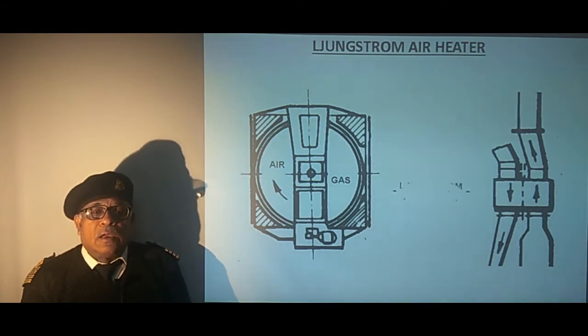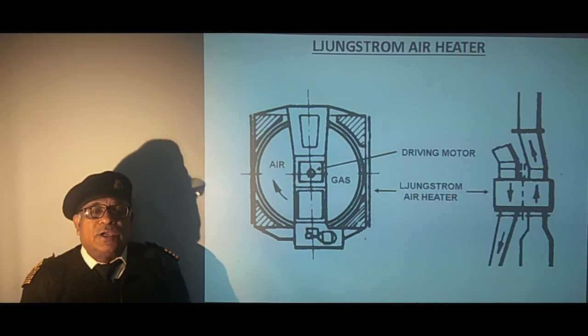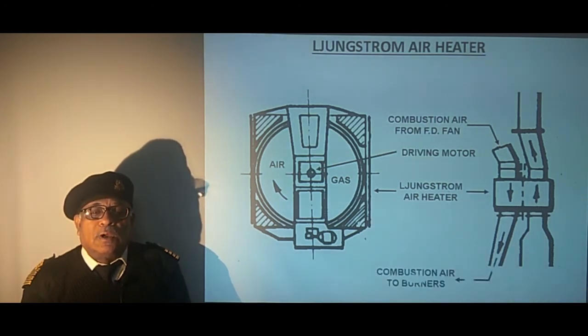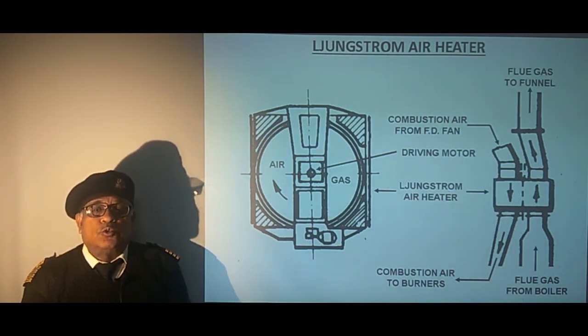So we can see this is known as Ljungstrom air heater and this is the driving motor which is shown which drive the rotor. And on either side of the center line we have gas and air passages as we can see on the right side. This is the combustion air from FD fan and it goes to the burners. Similarly the flue gas from the boiler passes to the heater and after heating the incoming combustion air it leaves the air heater and passes to the funnel.